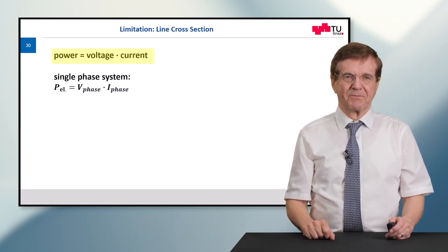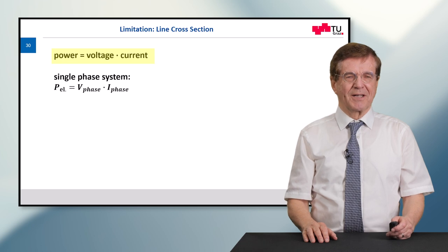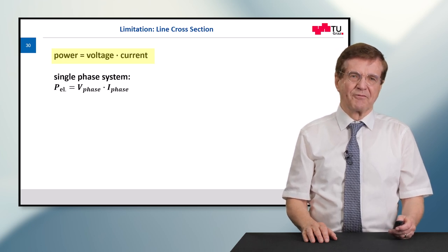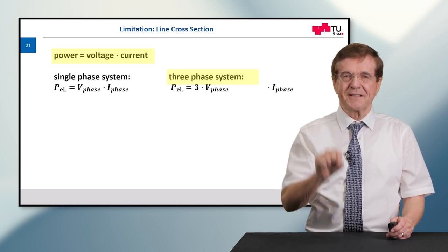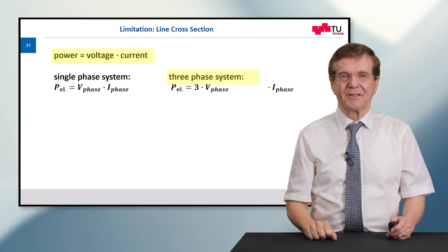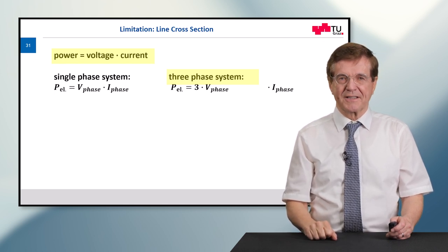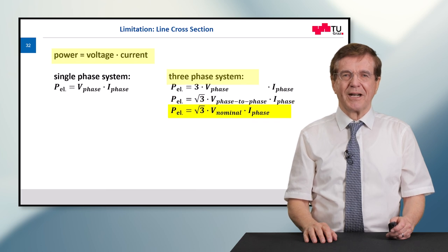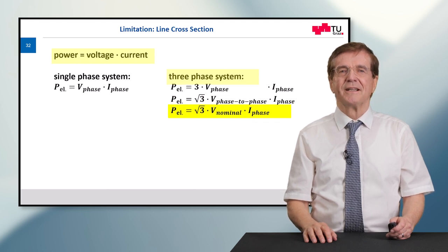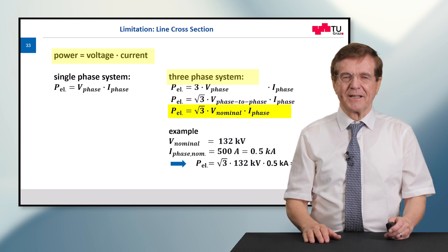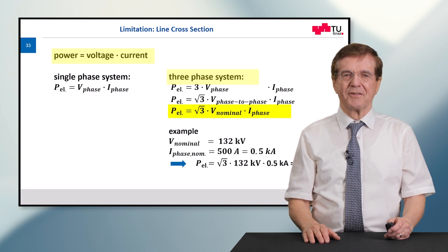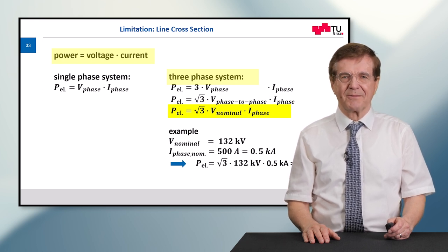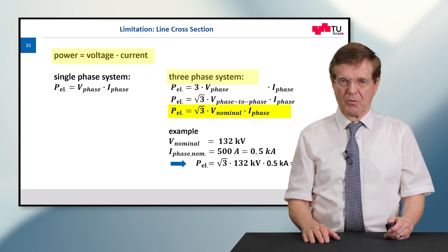Now a little calculation follows. Power is voltage times current. And in single phase system, this is the formula given for this: P is V times current. In a three phase system, we have three voltages, three currents, the so-called phase voltages, phase currents. And after some transformations, we arrive at the formula given in yellow. Don't be confused. I give you an explanation and an example. We assume that we have 132 kV overhead lines with a nominal current of 500 amps. And here we arrive that the maximum transportable power is something like 114 megawatts.